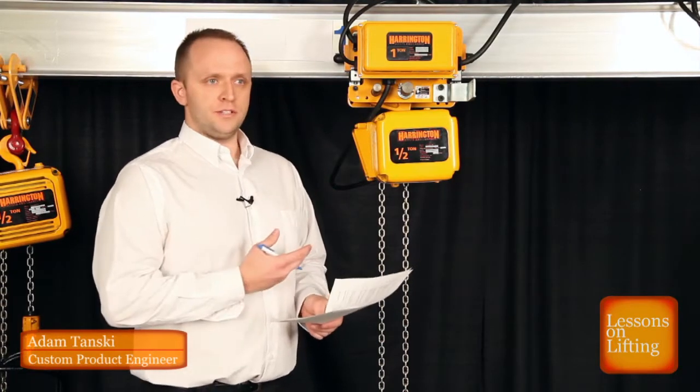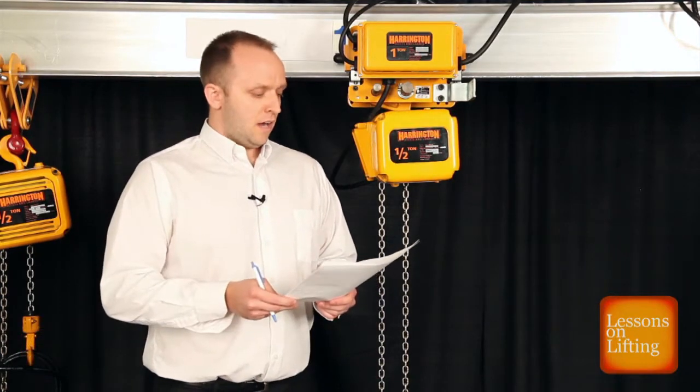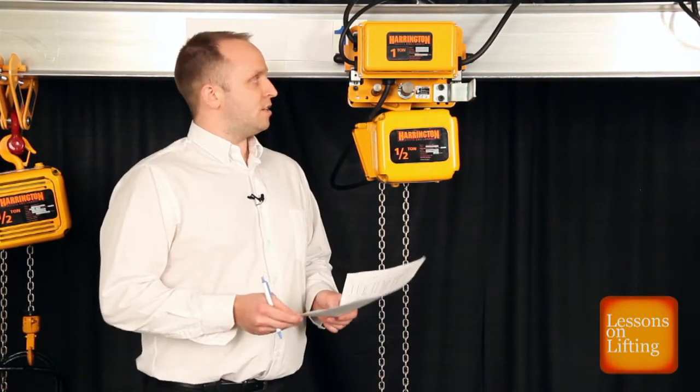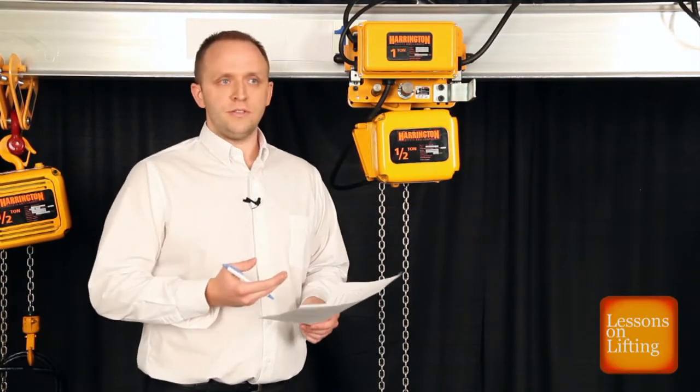Today we're going to be performing a voltage change on this ER2-MR2 trolley hoist. We're going to be changing this trolley hoist from 460 volt to 230 volt. These units are capable of running on 230 or 460 volt three-phase power.